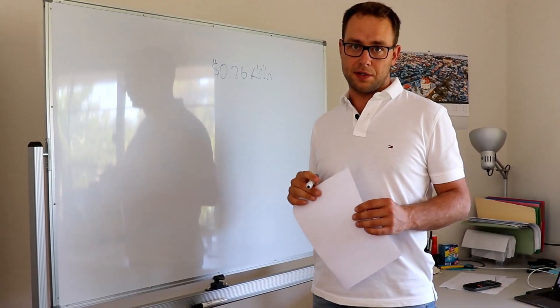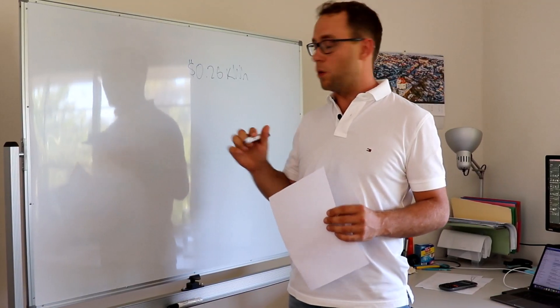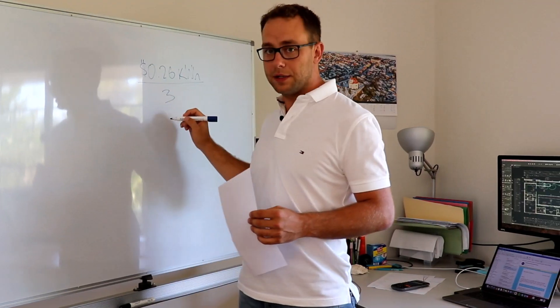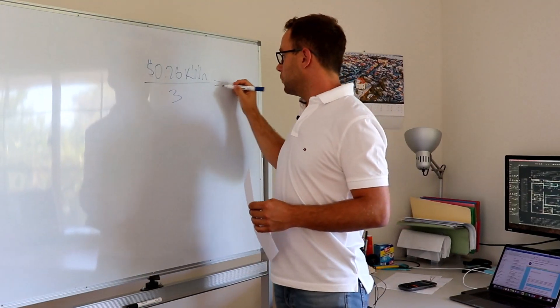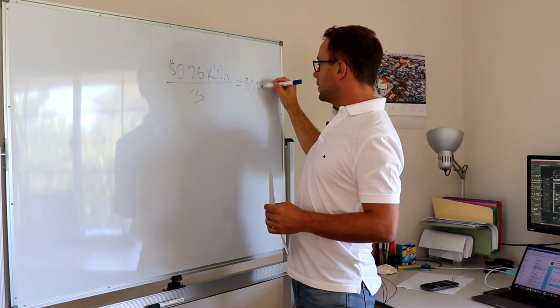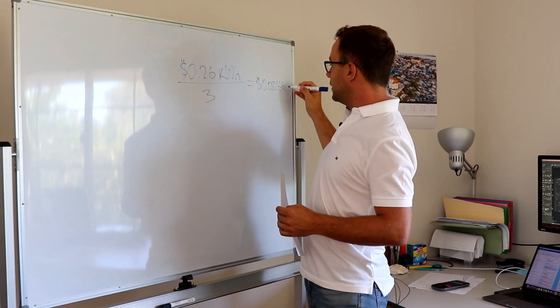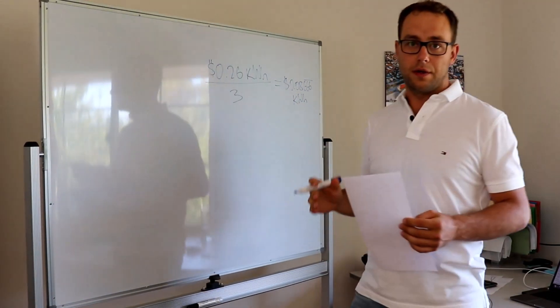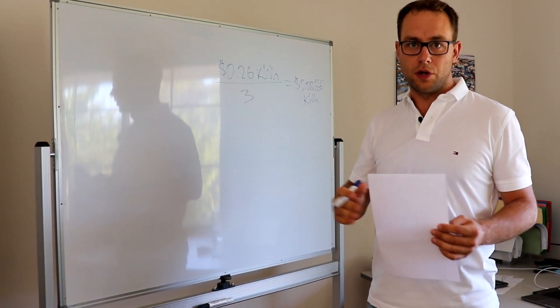Now because we have a 300% efficiency with the heat pump, what we can do is basically divide this by three and we know that we have now just under nine cents per kilowatt hour of input.